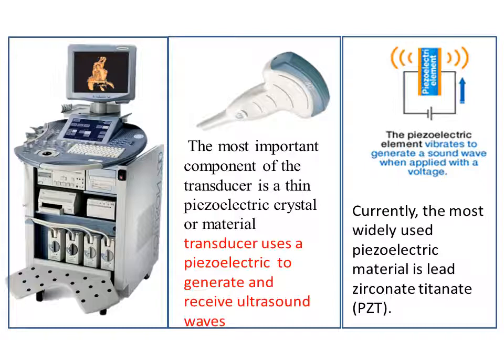An ultrasound scanner consists of three main components: a computer, a screen, and a transducer. The transducer has the ability to convert one form of energy to another. In the ultrasound device, the transducer converts electrical pulses into an ultrasound beam, sends this beam into the body, then receives the reflected ultrasound beam that carries information from inside the body. This signal is then processed and amplified before being displayed on the screen as a real-time image.